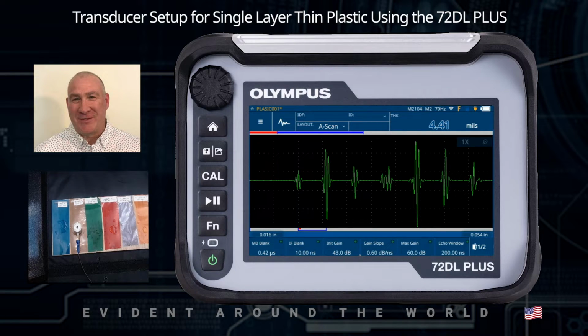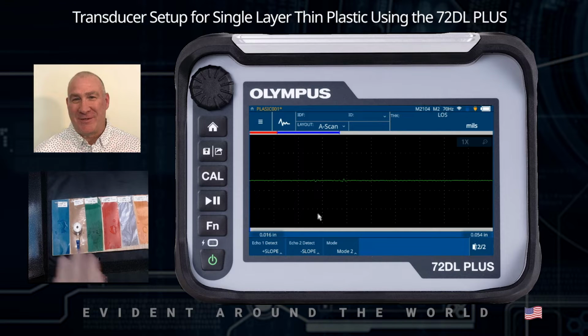So at this point, we want to check the polarity of the signal. The first echo is positive going, and the second echo, the back wall, is negative. So if we click on the adjustment here to go to the second page of parameters, we can go in and make sure that echo 1 is set at positive and echo 2 is set at negative. Okay, I'm going to hit the play pause key again to go back to a live measurement, and I'm going to check my shims.